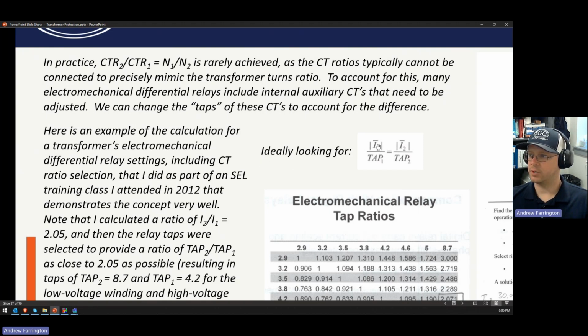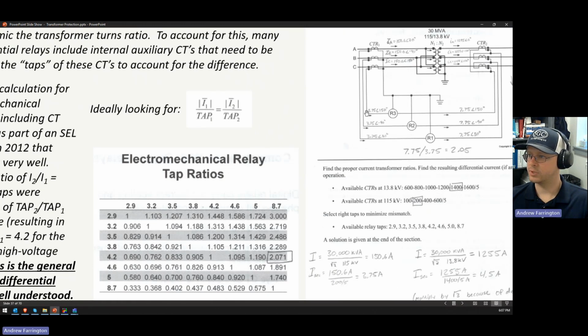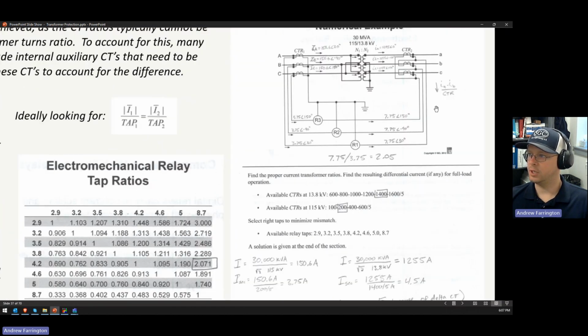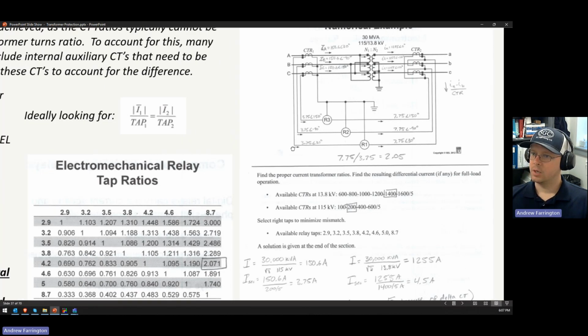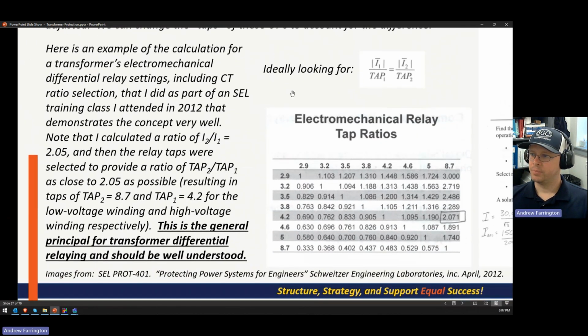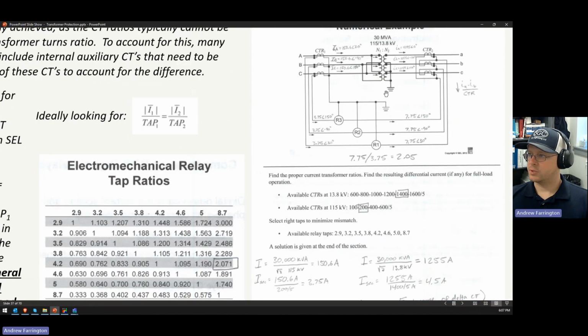And what you're ideally looking for is that the current seen on the high side of the transformer divided by the incoming tap, this is the tap 1 setting for this relay, is going to be equal to the current on the low side divided by the tap on receiving the low side current. So that's what we're looking for ideally. And again, this is a good example.